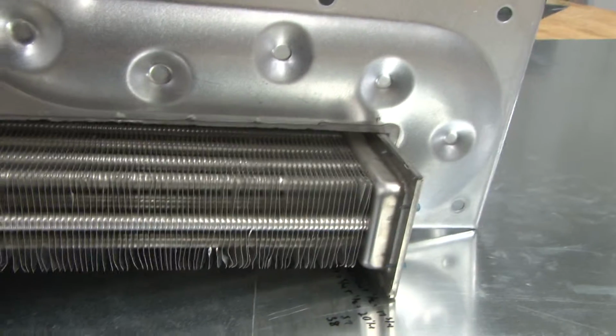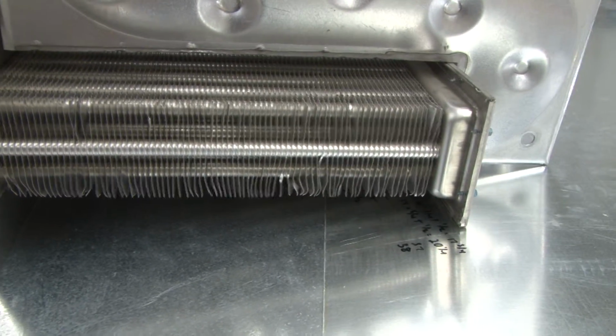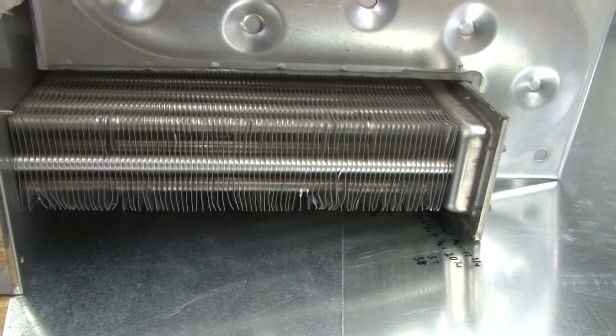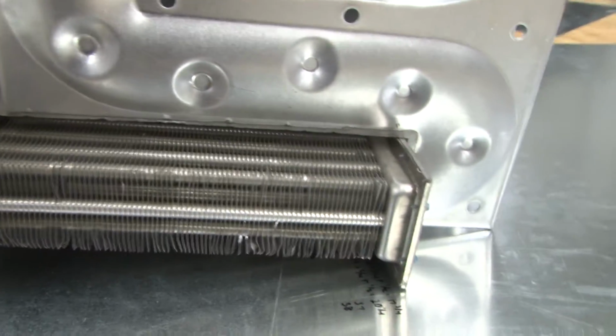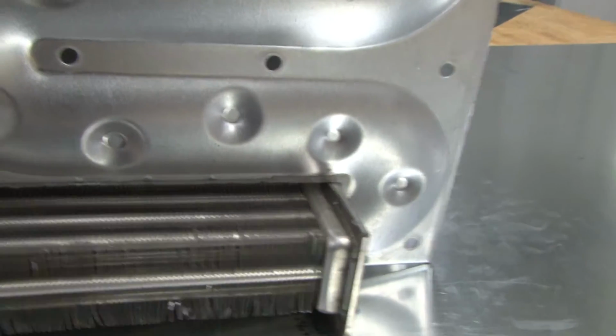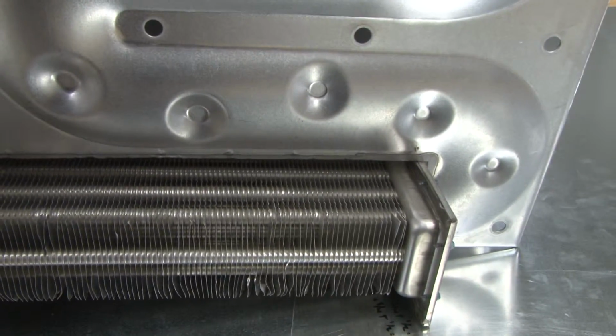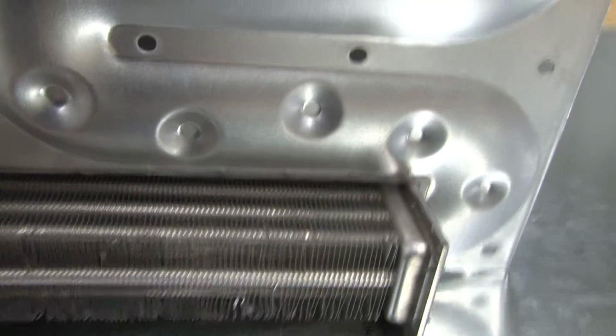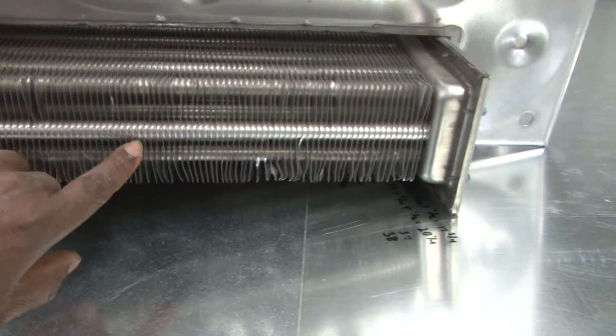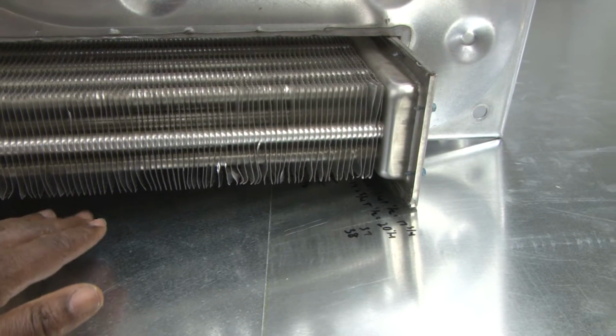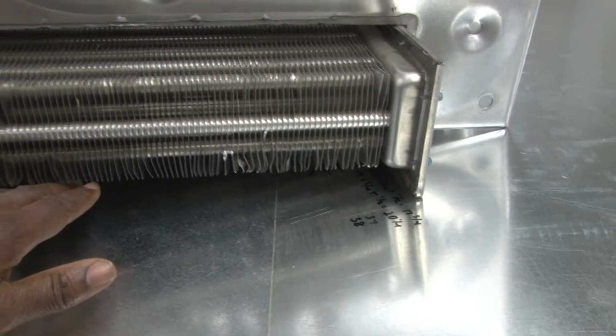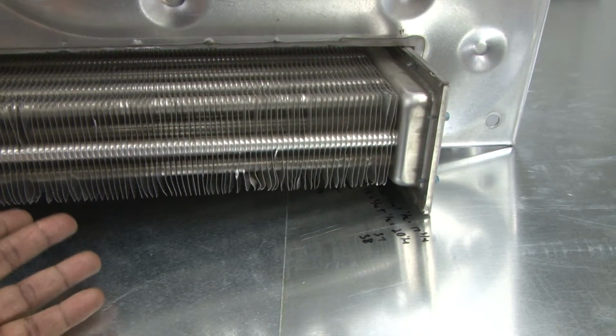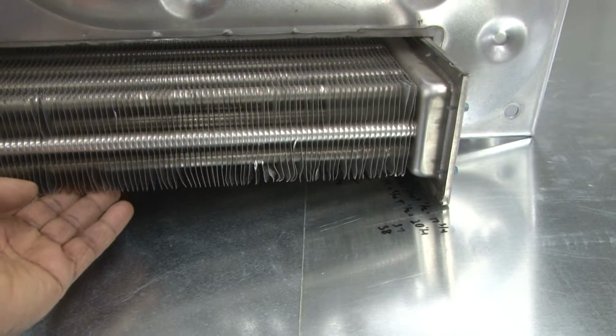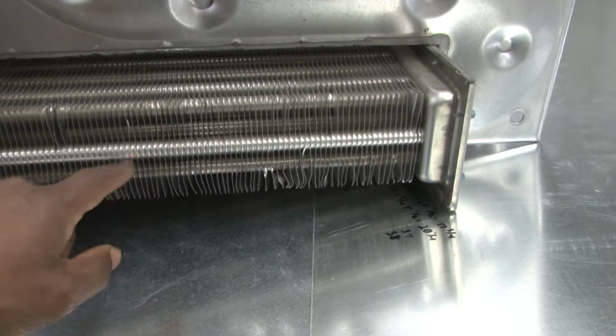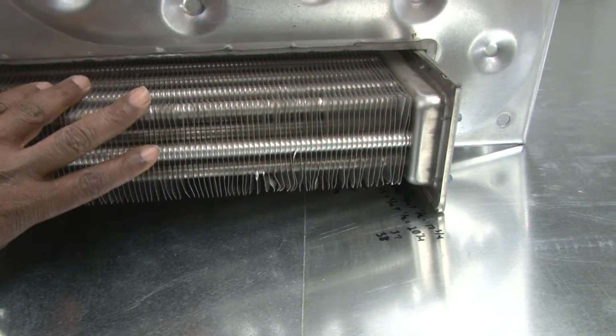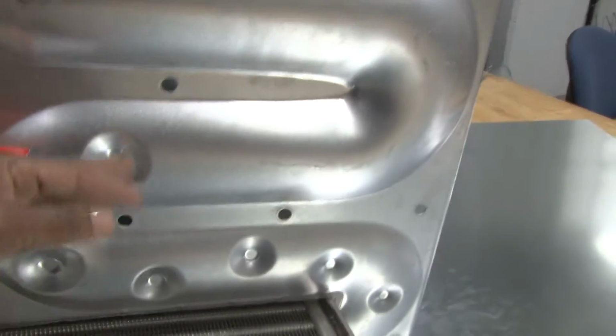The secondary heat exchanger is almost like a condenser coil. It's made out of stainless steel, but it has very small passages. These passages are used to separate the volume of flue gases which carry the heat, to be able to extract the heat from it more easily. Now, this secondary heat exchanger is located right above the blower wheel. So it's actually getting the coolest air touching it, to help have a very high TD to extract heat from the secondary heat exchanger before you even get to the primary heat exchanger.